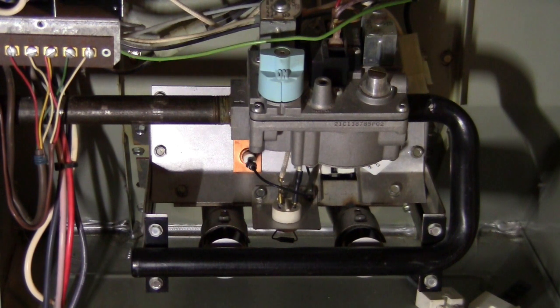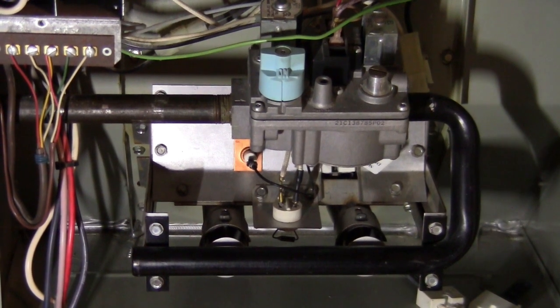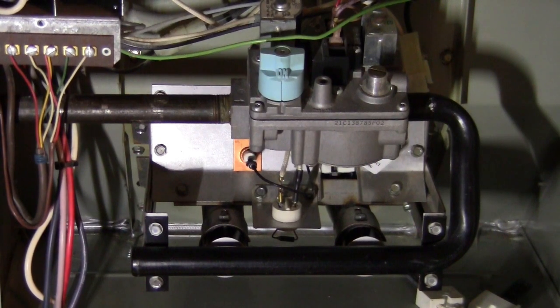But if I trigger it 2 or 3 times, like I turn off the switch, turn on the switch, turn off the switch, turn on the switch, then it stays. But at night time, with nobody there, the controller is going to make 2 tries to start it, and after 2 tries it fails. It just sits there and blows cold air. Only the exhaust fan is running, and the other things are not running. That's my problem since last week. So I replaced the sensor. It's still not working, and eventually I have to replace this controller.